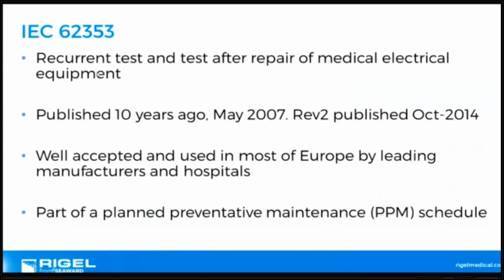So with 62353, this is the standard that is designed for recurrent testing, designed for after repair and the preventative maintenance schedule, but still within the same safety criteria as 60601, i.e. measuring hazardous leakage currents, both the means of patient protection and means of operator protection. Well accepted in parts of Europe. What I have seen, especially in North America, is part of this alternative equipment maintenance schedule. Well, if you were testing to NFPA 99, the manufacturers say, no, we want you to test this to 62353. Typically, if it's being manufactured in Europe, well, you need a safety analyzer to do this, and you need some kind of understanding. And this is why I'm keeping this presentation relatively global.